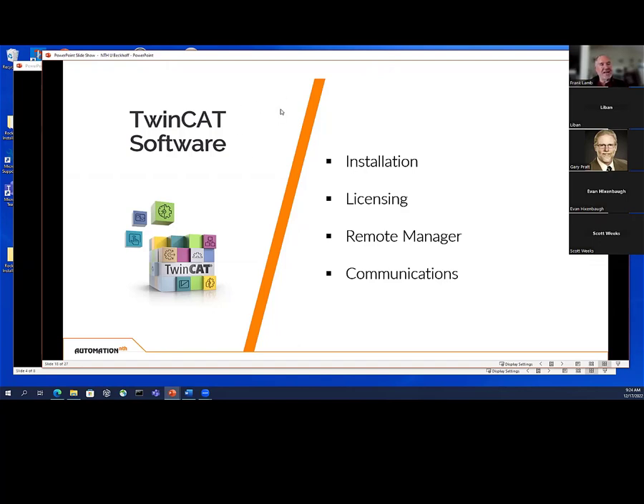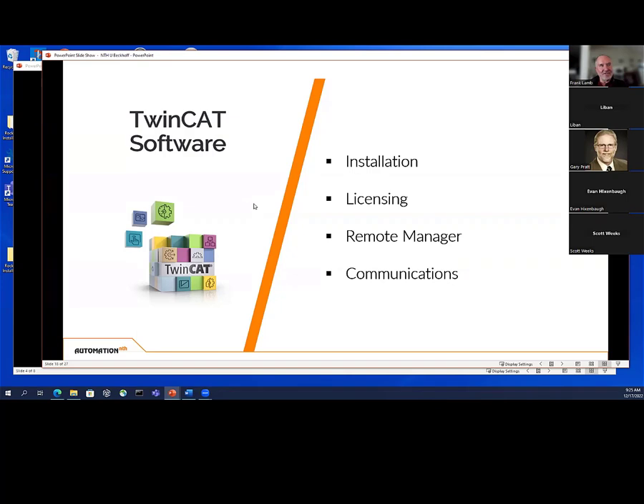I keep reminding myself — this is not a PLC, it is a computer in every way. Things like configuring your communication ports, you don't do that through TwinCat. You do it like you would a computer — you get in there and configure the ports that way. There's very little you can do to configure ports within TwinCat software itself. You have to set up your routes and all that, so we go over communications a lot.